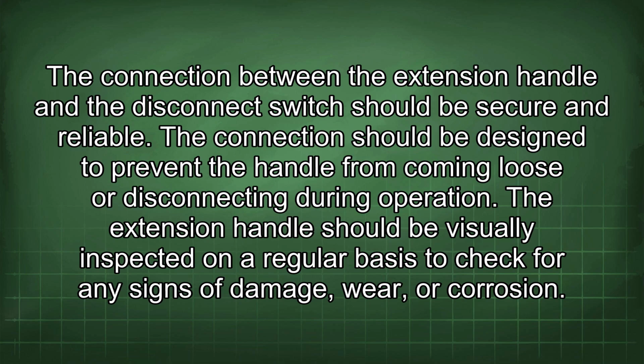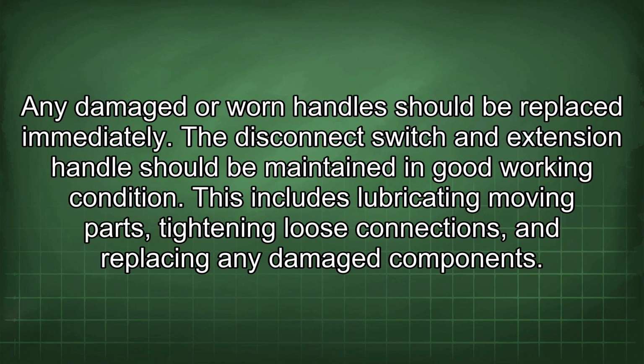The connection between the extension handle and the disconnect switch should be secure and reliable. The connection should be designed to prevent the handle from coming loose or disconnecting during operation. The extension handle should be visually inspected on a regular basis to check for any signs of damage, wear, or corrosion. Any damaged or worn handle should be replaced immediately. The disconnect switch and extension handle should be maintained in good working condition. This includes lubricating moving parts, tightening loose connections, and replacing any damaged components.